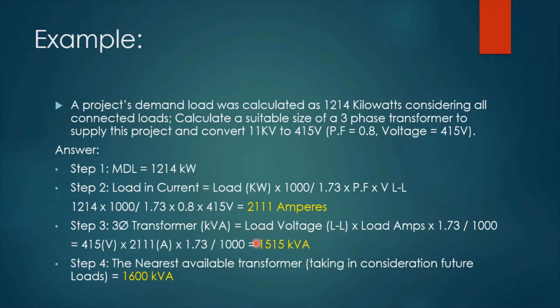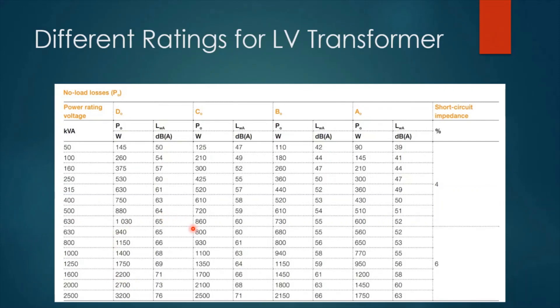Based on this value of 1,515 kVA, we look into the nearest available transformer in a manufacturer's catalog. Taking future loads into consideration, the nearest available transformer is 1,600 kilovolt amperes. From the table included here, the suitable size for our example is 1,600 kilovolt amperes — the nearest to 1,515 kVA. 1,250 kVA would not be suitable, and 2,000 kVA would be more than needed and more costly. So 1,600 kVA is the suitable size for our transformer.